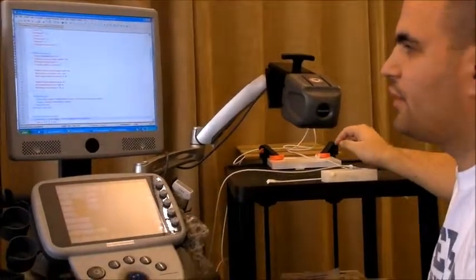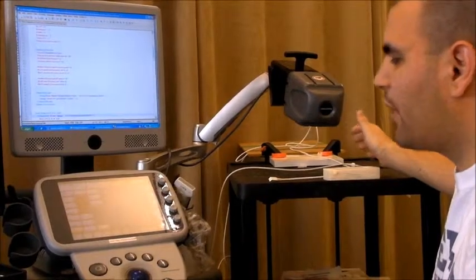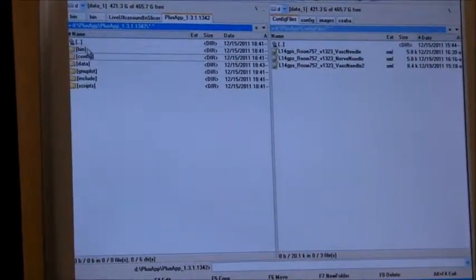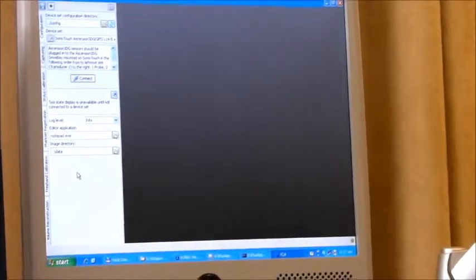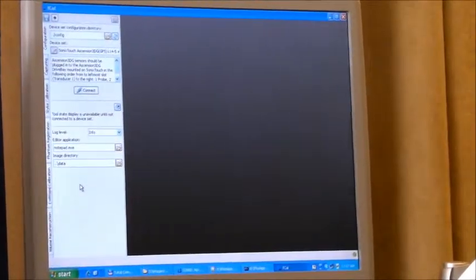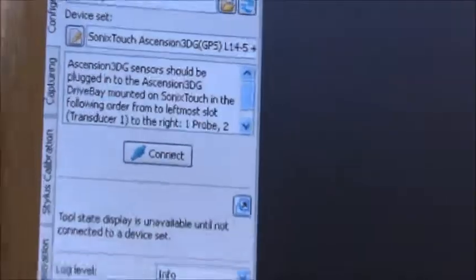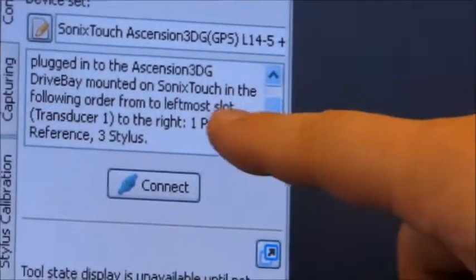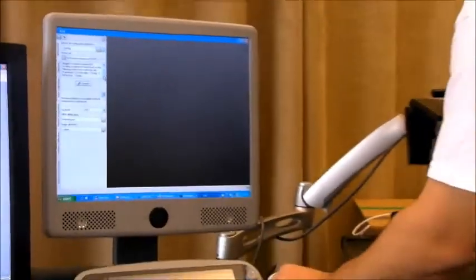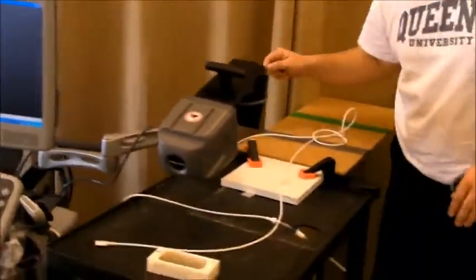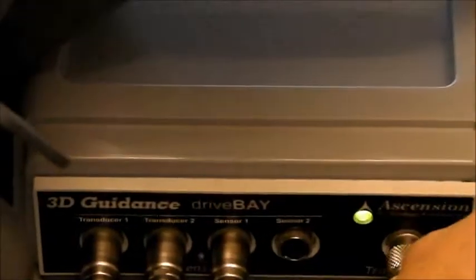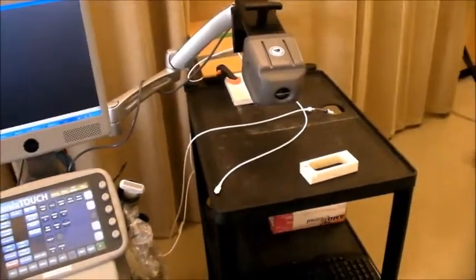And then, before we use the pointing device, I want to make sure that the stylus tip to stylus, so the pivot calibration, is correct. So we are going to run that now quickly. So I'm opening fCal. And before I connect to the devices, let's make sure that they are plugged in the correct order. The device set description says that from left to right, the tools should be plugged in as probe, reference, stylus. So the probe is obviously this one. Have a look at the plugs. The leftmost is the probe, the second one is the reference, which is just this, and then the stylus is the needle.